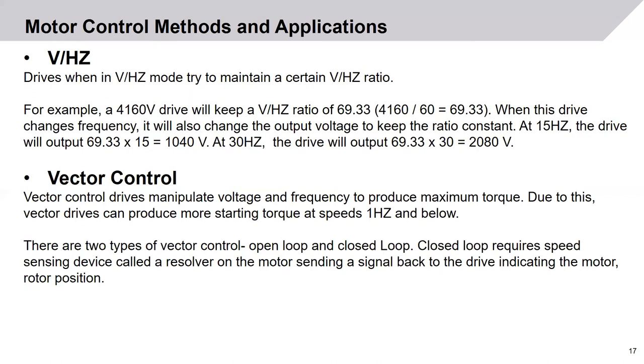Vector control is somewhat different. Vector control drives manipulate voltage and frequency to produce maximum torque. Due to this, vector drives can produce more starting torque at lower speeds — below one hertz. There are two types of vector control: open loop and closed loop. Closed loop requires a speed sensing device called a resolver or tach feedback on the motor, sending a signal back to the drive indicating motor rotor position. In open loop control, there is no resolver or tach feedback — the drive algorithm simply manipulates the operation.